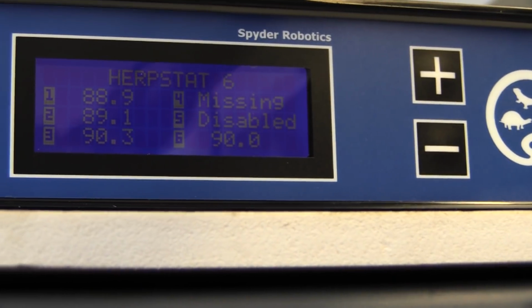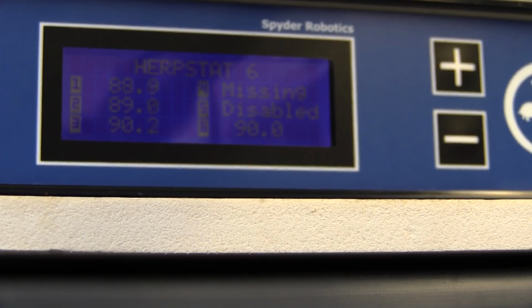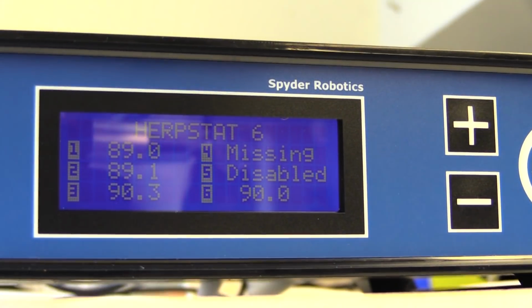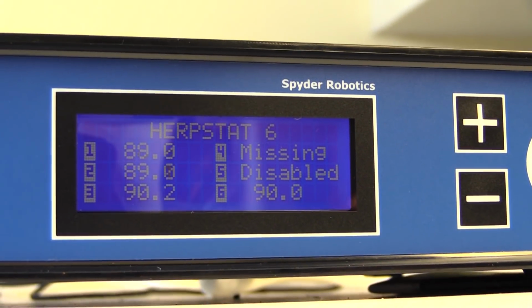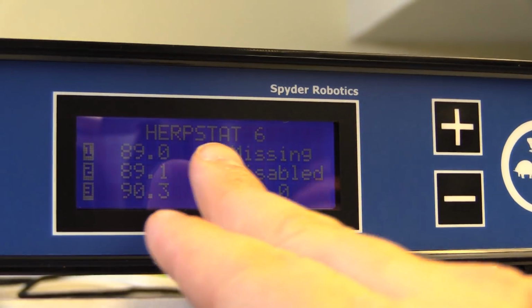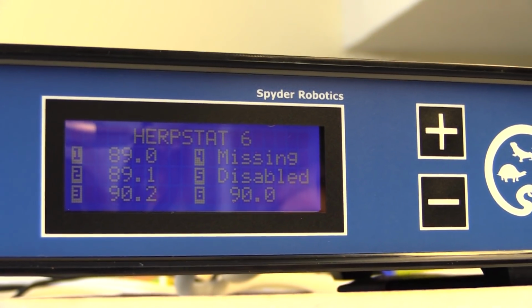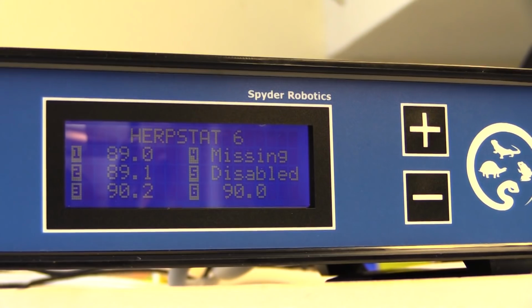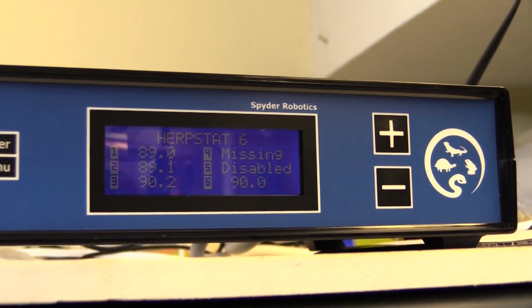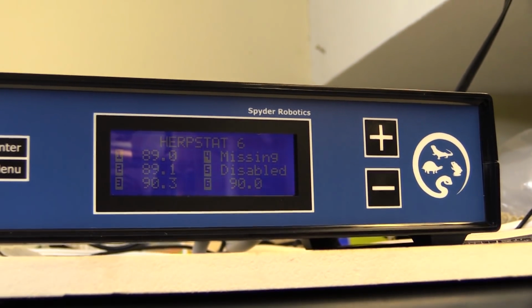Takes a second. And look, it says probe missing. You hear that beep? That's the alarm telling me, hey, idiot, there's a problem. It says probe missing, because there's no probe plugged in. So it's recognizing that the probe is missing, setting an alarm to tell me it's missing or failed, and it's putting no heat to it.